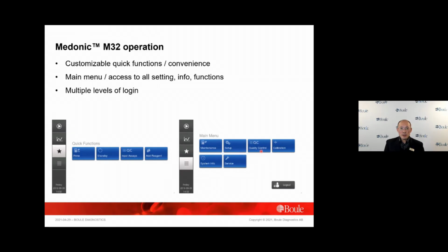The QC menu is for long-term monitoring of instrument performance by the XB and LJ, and also for control blood input. Calibration has two levels: guided, which can be performed by the end user, and advanced, which is usually done by the service engineer.